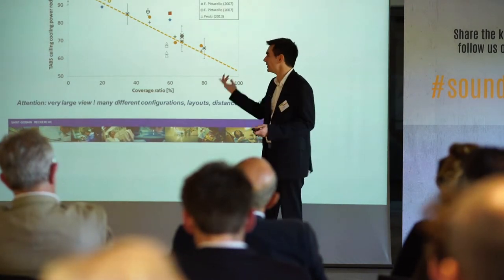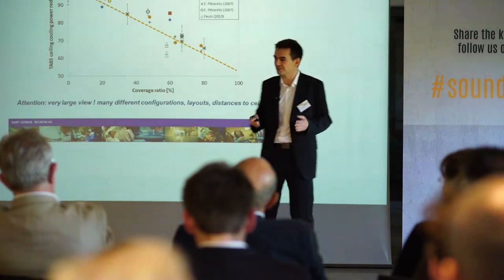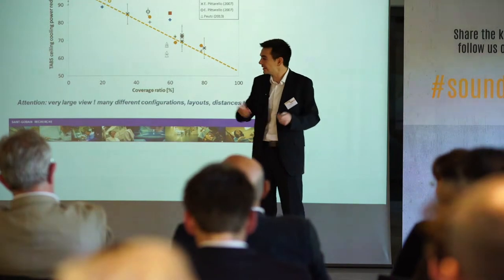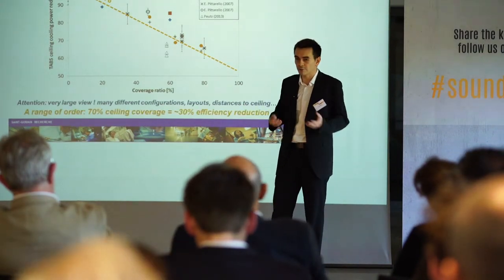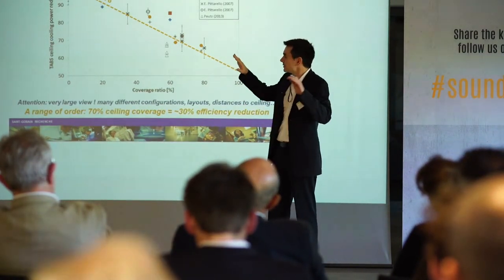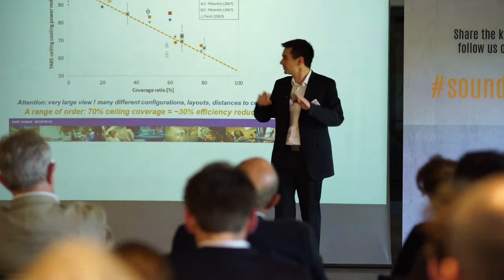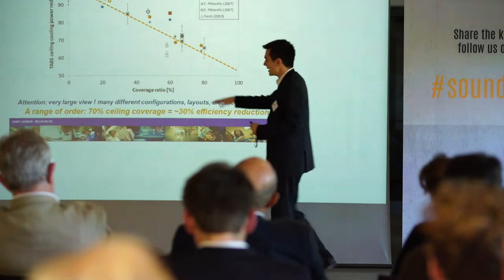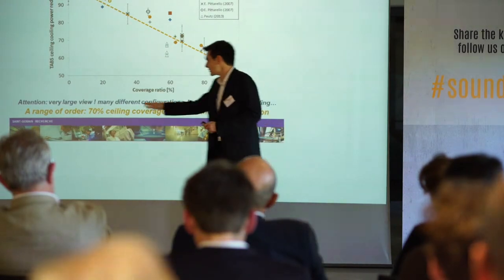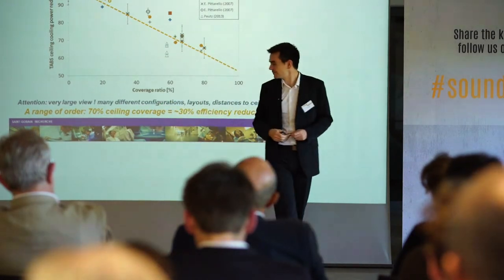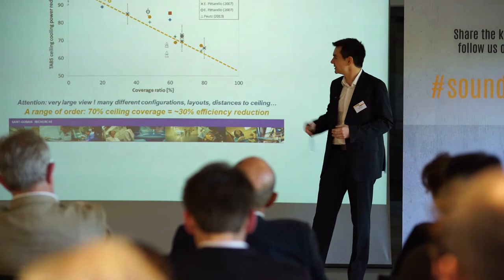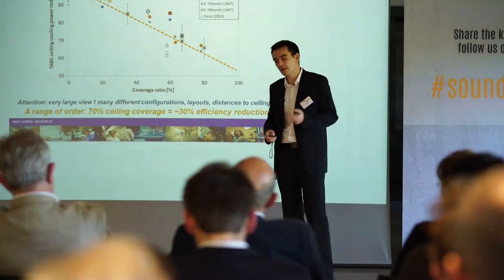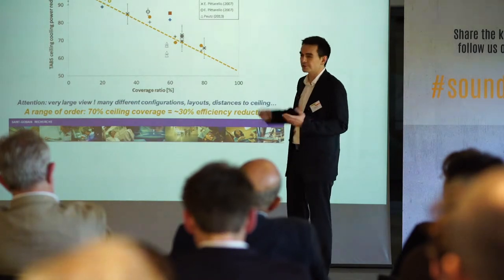Just to remind you, a very good value of such a coefficient is 0.99, for example. But here we have a very broad view. Just to give an order of magnitude, comparing all configurations and all experiments on the same graph, we can see that if we cover 70% of the ceiling, we reduce the efficiency of the TABS cooling by around 30%. That's useful information, but here it's just the efficiency.